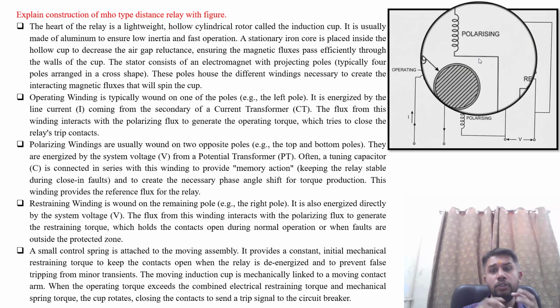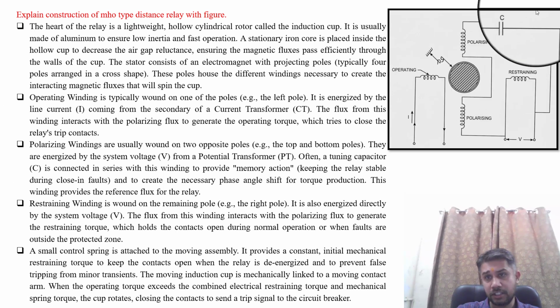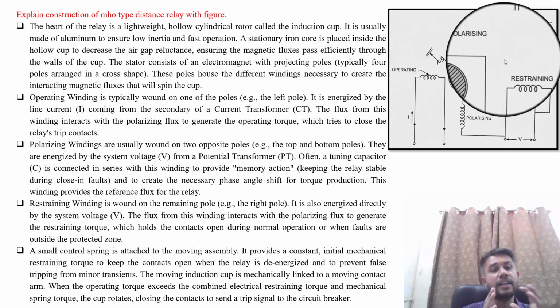Often a tuning capacitor, you can visualize this tuning capacitor, is connected in series with the winding to provide memory action. This memory action is necessary for keeping the relay stable during close-in faults and to create the necessary phase angle shift for torque production. This winding provides the reference flux for the relay.